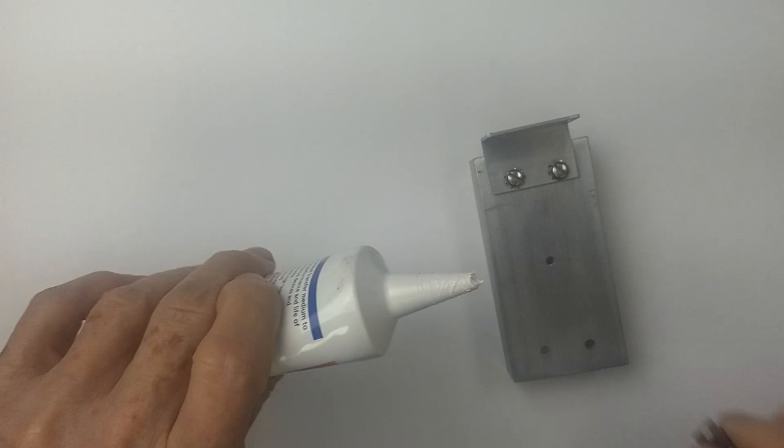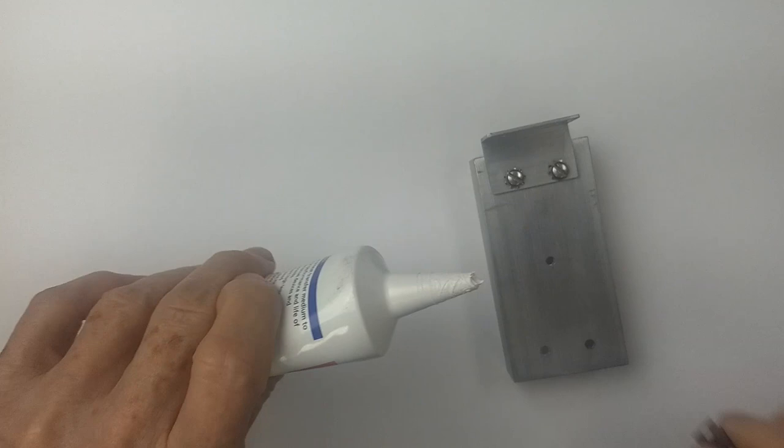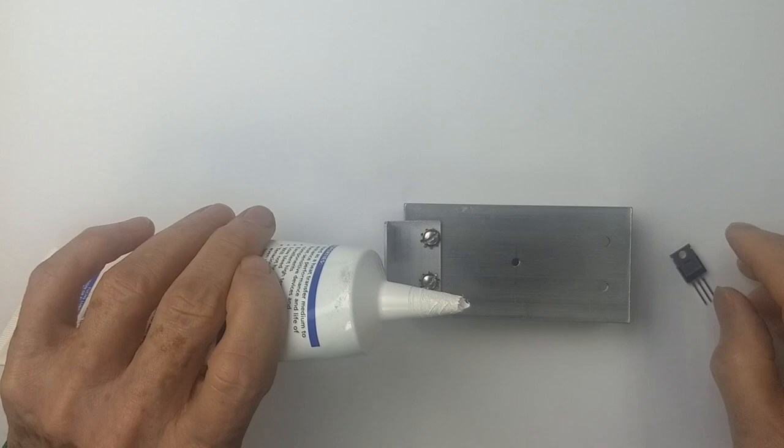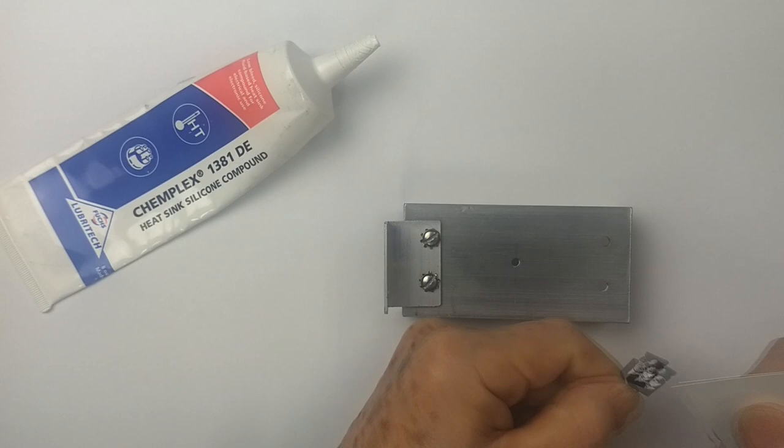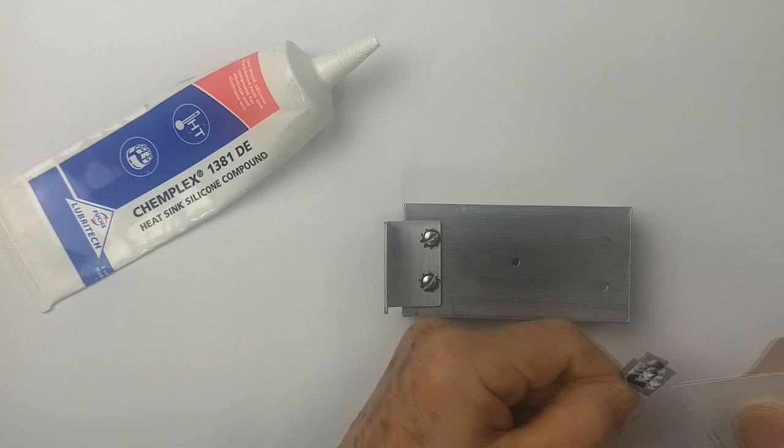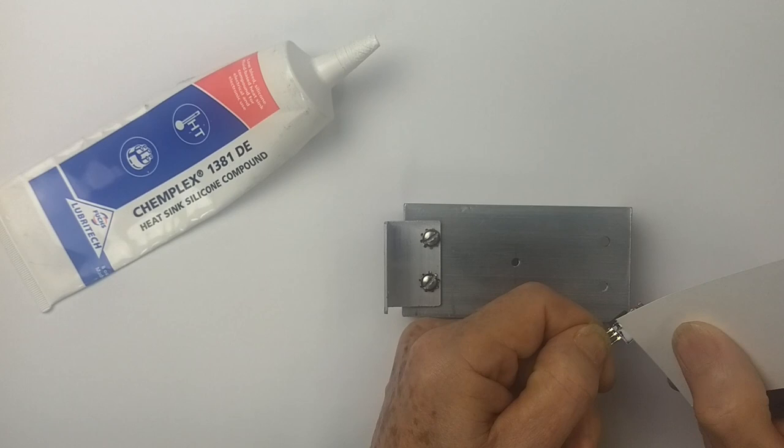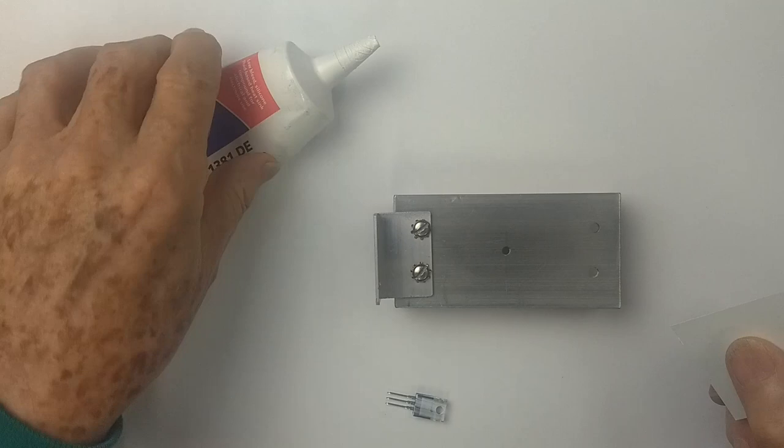Now we're going to mount this device on this heat sink. So what we want to do is apply a little bit of the compound, and then with something like a business card, we want to spread it around, and then wipe the majority of it off.